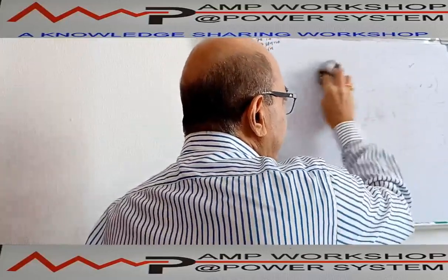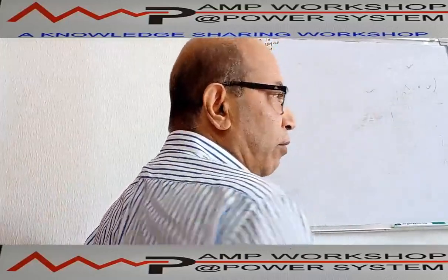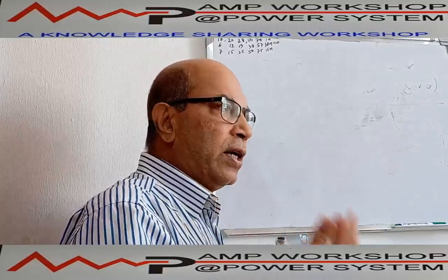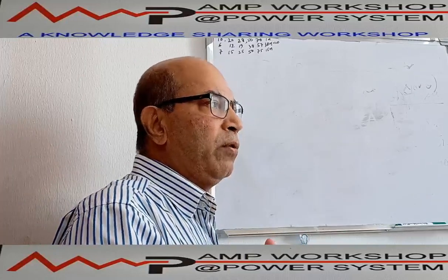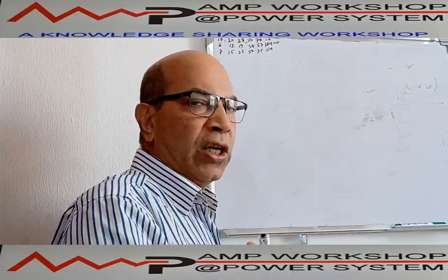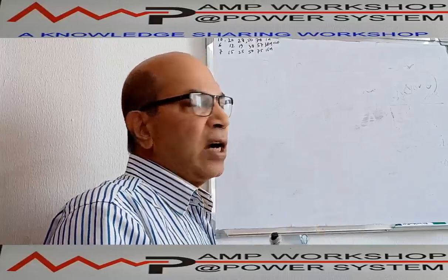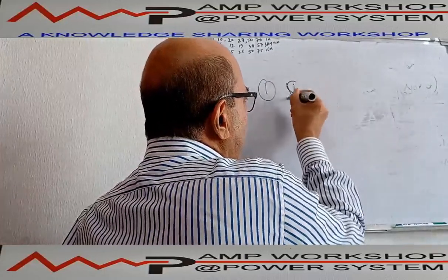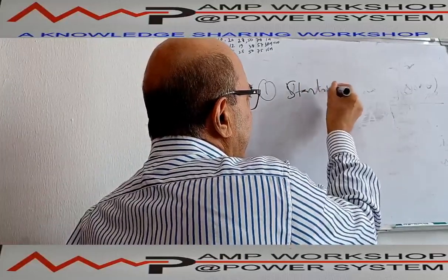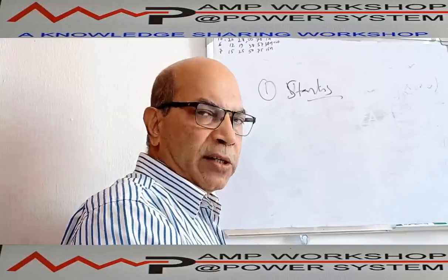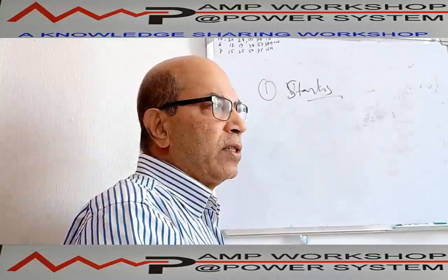But in case of motor cable, when we decide the motor cable, we have to calculate the continuous current rating of the cable from the voltage drop point of view, as well as we have to calculate the starting with that cross section area. We have to check the starting voltage drop. One additional voltage drop calculation is required. That is a motor starting voltage drop calculation, because as per IEC we say that motor should start at 80% voltage.